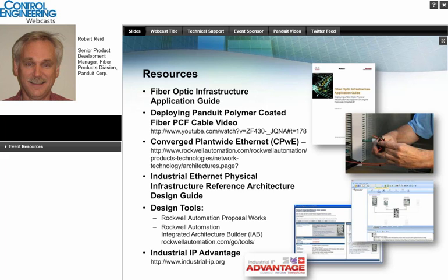Most people don't realize that grounding and bonding is important, but it's espoused by standards for backbone cabling, as an example. Even though it's fiber, it has a metallic conduit. The conduit must be grounded. And as I mentioned earlier, EMI, as an example, is one of the things you want to kill with grounding. Fiber is impervious to EMI, but transceivers are not. So in very noisy environments, higher speed transceivers in particular, beyond 1 gig, are somewhat susceptible to EMI.